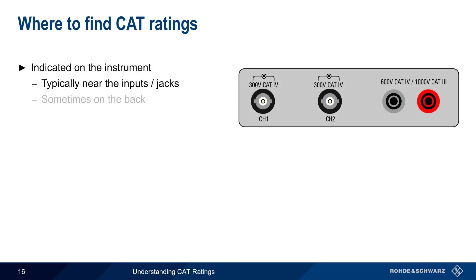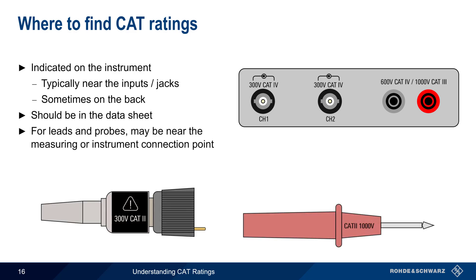How do we determine CAT ratings? These are normally indicated on the instrument itself, typically near the actual inputs or jacks, but sometimes found on the rear of the instrument. Naturally, this information should also be contained in the instrument's specifications or data sheet. For DMM leads or oscilloscope probes, the CAT rating is sometimes printed near either the measurement point or near the instrument connection point. The DMM probe caps mentioned earlier will sometimes also have CAT and rated voltage values printed directly on them.